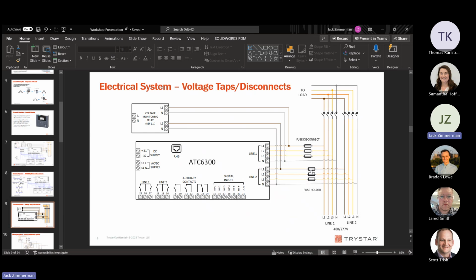And then we have another set, this is not a disconnect, but a fuse holder. So it's just protecting the controller from a fault condition, because remember, these are being tapped from the bus bar. There's no overcurrent protection on the utility side typically, because it's coming straight from the utility transformer. So we need overcurrent protection there because you have, I don't want to say infinite fault current potential, but a lot of fault current potential coming straight from that utility transformer.